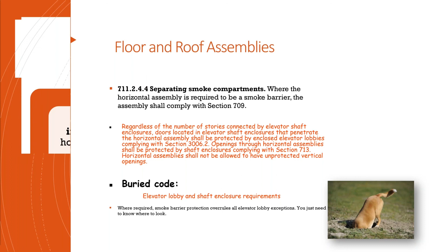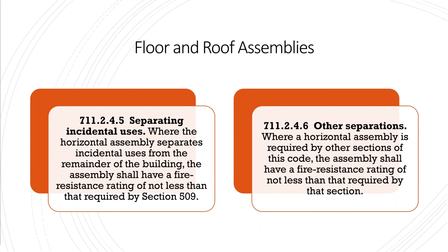When you're separating incidental uses, go to 509. Again, very similar to fire barriers, right? The sections tell you where to go when you have to have these separations. Go to 509 for determining the rating that you need for incidental uses, and then other portions of the code will tell you what those separations are required to be, what the ratings are required to be for those separations. Like again, that energy storage system like we talked about.